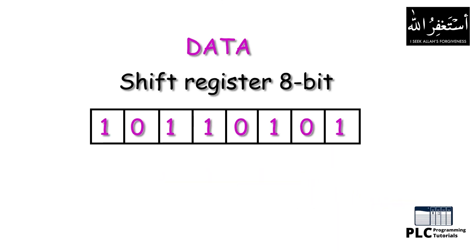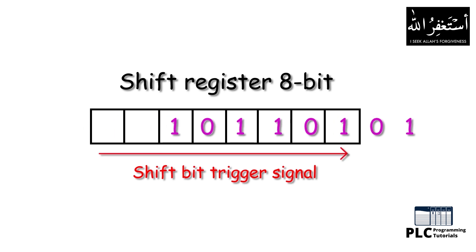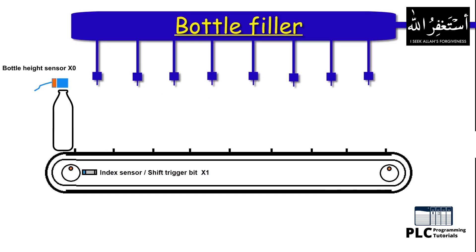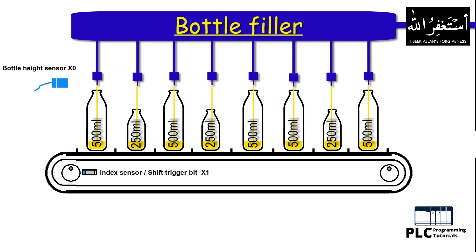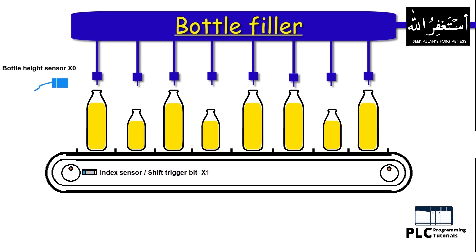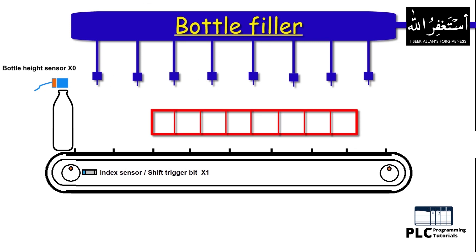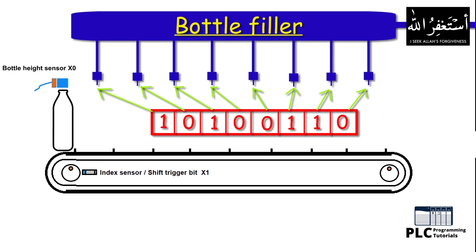So far we have learned that a shift register has some data inside it and it is shifted or rotated across the register each time the shift instruction is triggered. Now let's see an example so we can understand how to use a shift register to execute complicated tasks in an easier way. Here we have a bottle filler with eight filling nozzles, and this filler will be filling two different size bottles — 250 ml and 500 ml. We can imagine these eight filling positions as the eight data bits of the shift register, with data bits inside it corresponding to the size of the bottle under each filling nozzle.